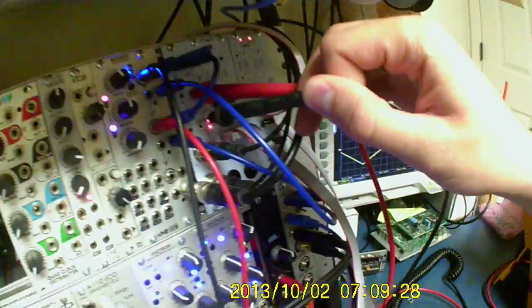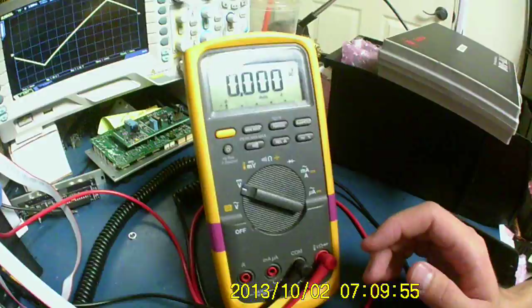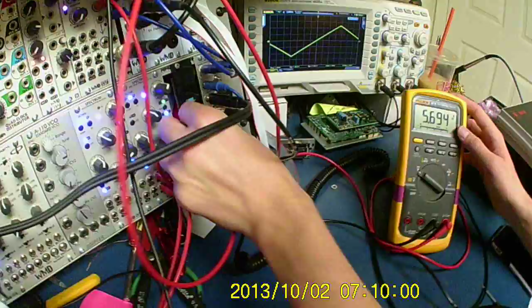So first thing you're going to want to do is just have a steady voltage source. So we have this module here that just outputs 0, 1, 2, 3, 4, 5, and 6. But you'll just want to set it up to 0 volts and then 6 volts, exactly. I always check this to make sure it's calibrated. So when it says 0 volts, this thing will read out 0.000 as long as all of the connections are solid. And then go up to the 6 volts.